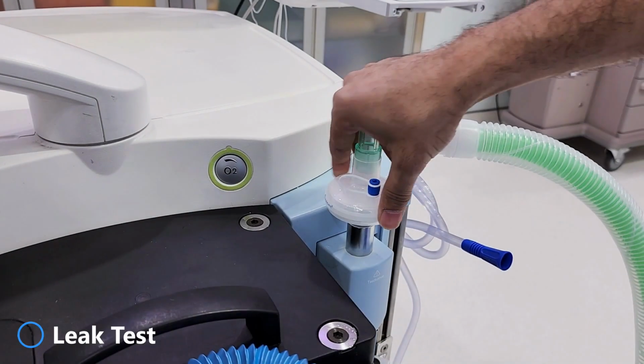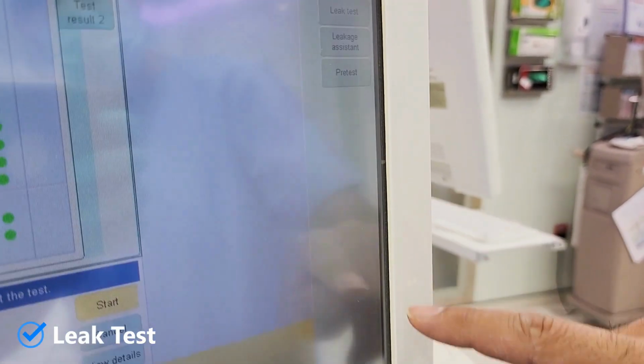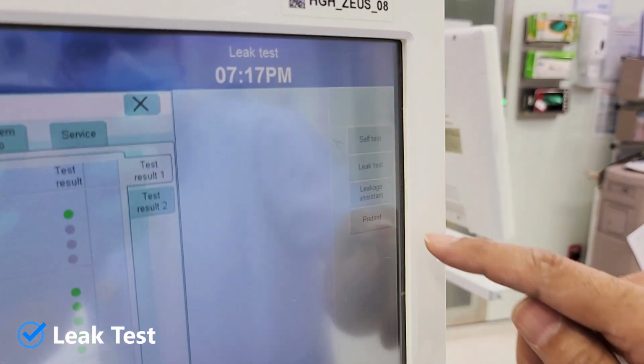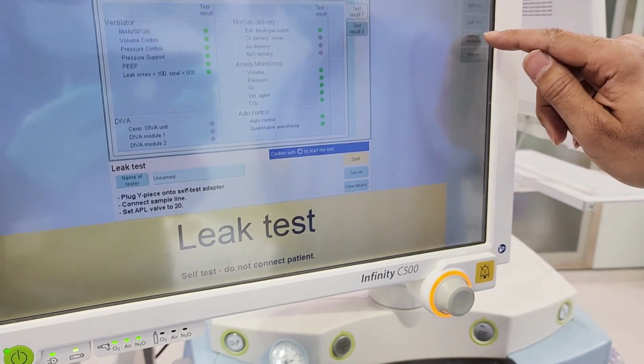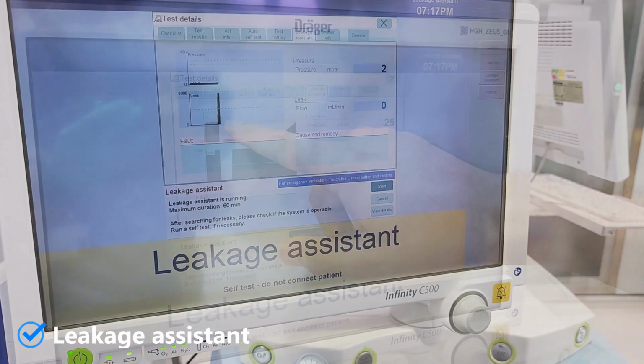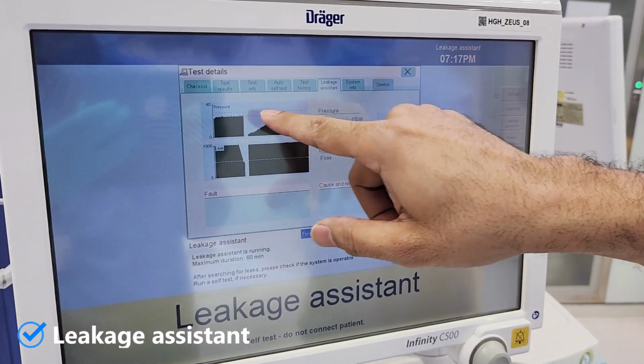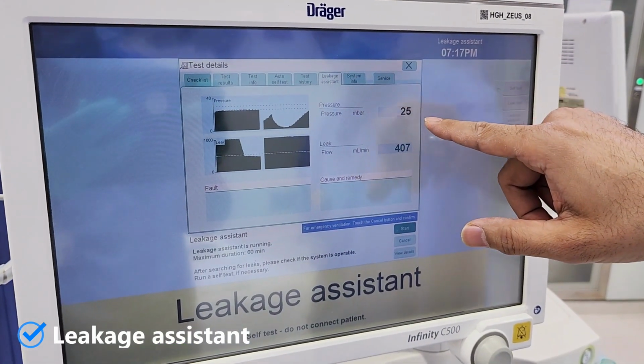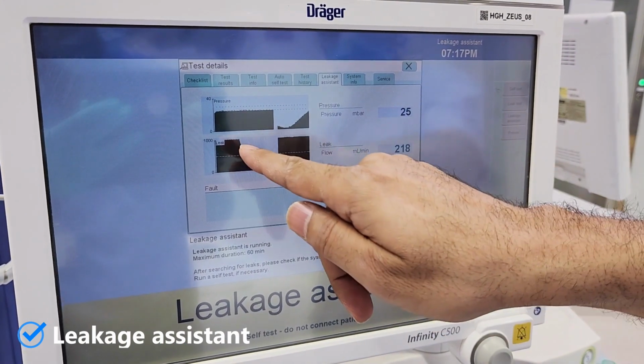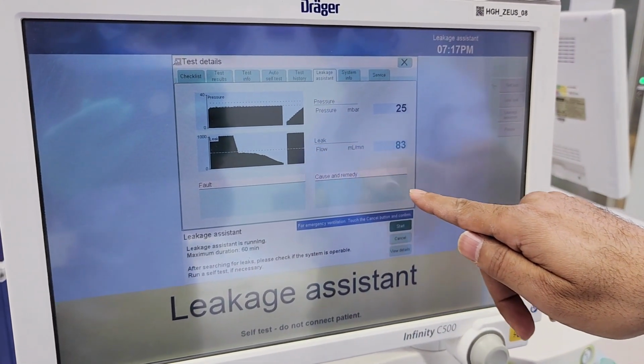The leak test can be performed between cases when you change the filter, circuit, or soda lime. This test takes around 4 minutes to finish. Leakage assistance can be done only when the machine is on standby mode to make sure there is no leakage in the breathing system. As you can see, pressure will be maintained at 25 millibars and leak flow will show in milliliters per minute. This test takes less than 1 minute.